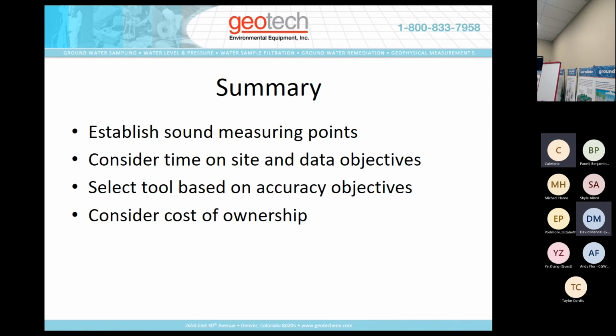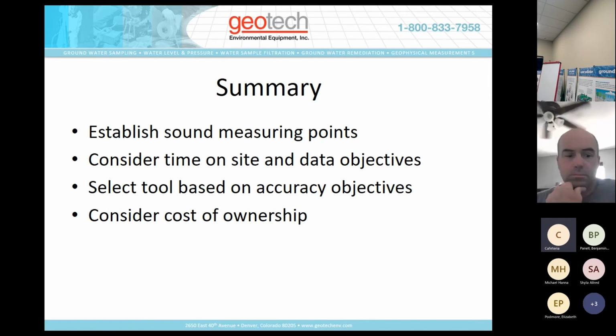Just to build off that, would having a dedicated pump installed affect the sonic reader? It can be compensated for. Well diameter, and the level of accuracy, from a practicality standpoint - if the pump is submerged and the only thing coming out of the water table is the tubing and/or motor lead, you can still adjust to compensate for whatever obstructions may be. If you have a sounding tube in the well, I think you're better off, all things being equal, than if you don't.